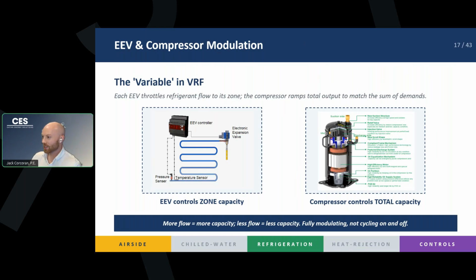And so the other side of the story, right, the other side of our refrigeration cycle, is our compressor, right? In VRF systems, it is a variable speed compressor, right? So you can imagine if you are closing your valves in some zones, you can't just keep cranking that. I guess a better way to think about it is your EEV is your zone level control and your compressor is your total system capacity, right? So if all your zones are calling for full heating or full cooling, that compressor is at its full speed, right? Because you need as much refrigerant flowing as you can to get to every single zone.